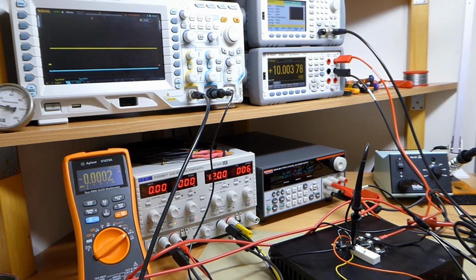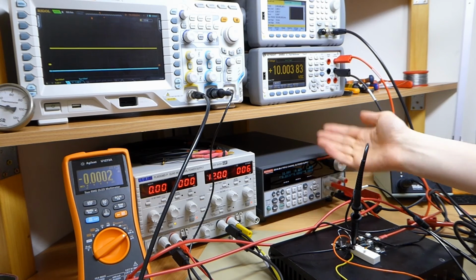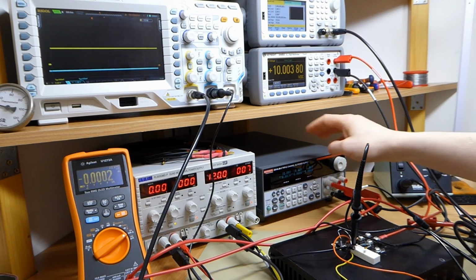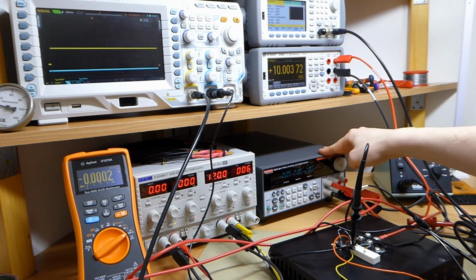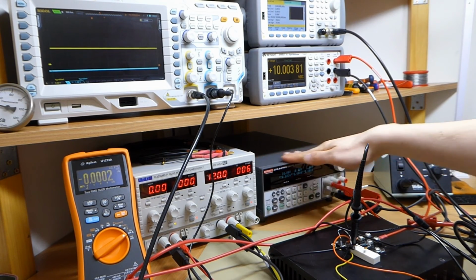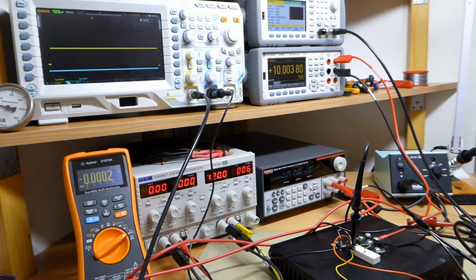There's nothing really wrong with that approach as such. The only downside is that if you have a load that draws pulsed currents, you can go into current limiting mode regularly, which also means your transformer taps are switched regularly. So every time you draw a current pulse, the relays in there might switch, which isn't great for the life of the relays, and depending on how the power supply is designed, it might also not be great for the power supply.